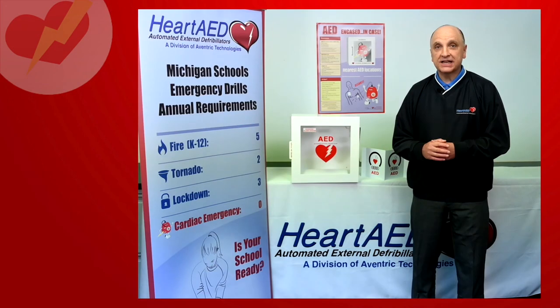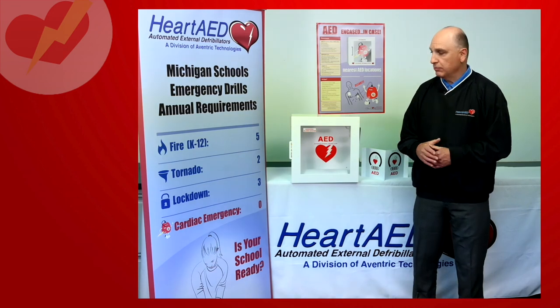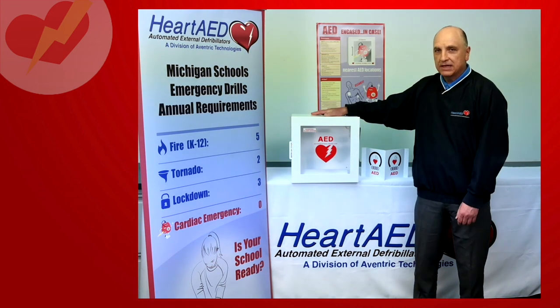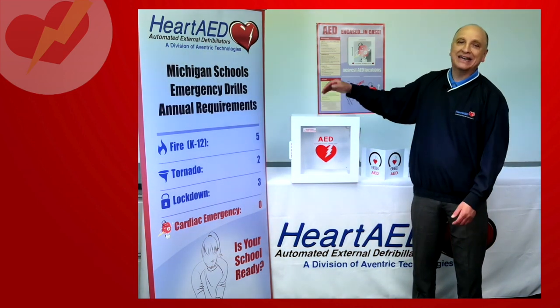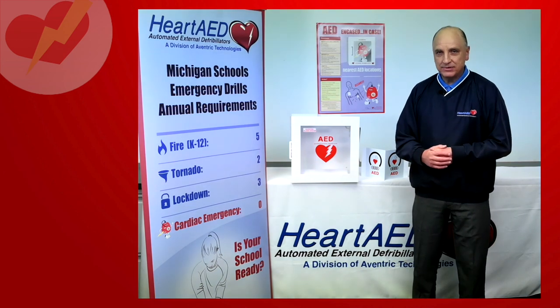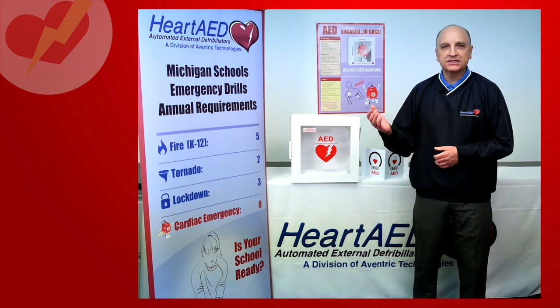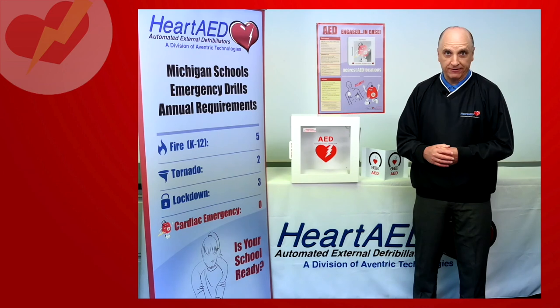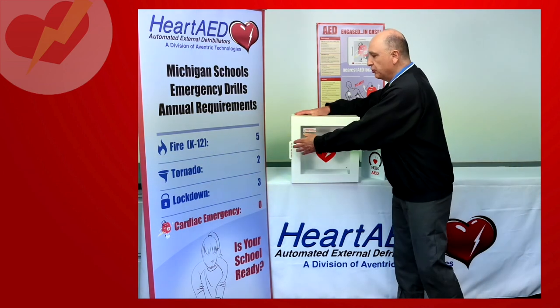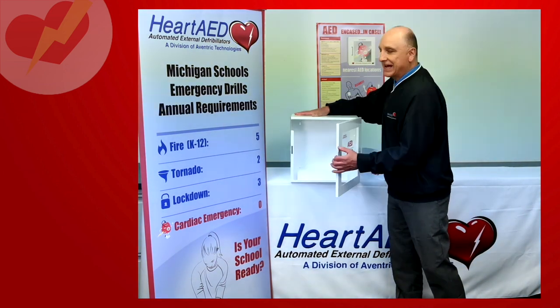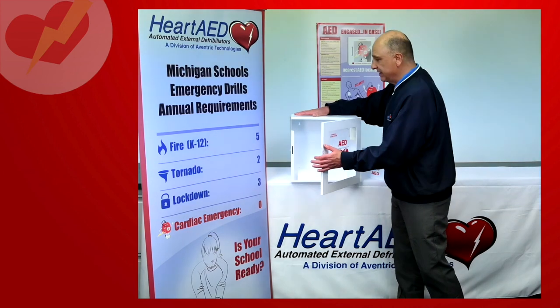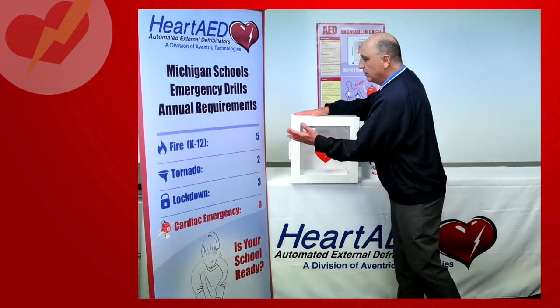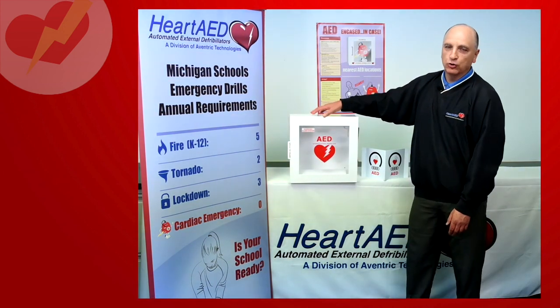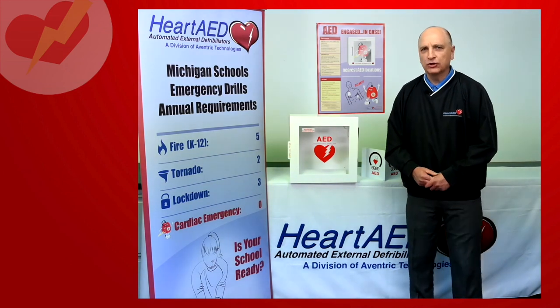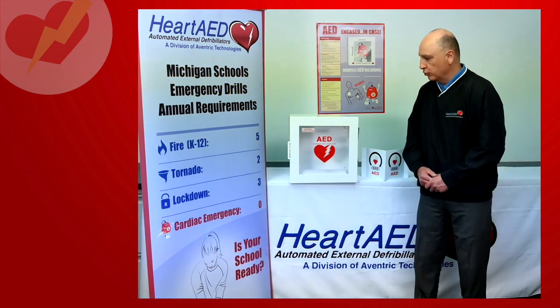A couple last items as it relates to your automated defibrillator. They're mostly stored in a wall cabinet. AED wall cabinets do not have locks on them. You may see keyholes, but that's basically to turn an alarm on and off. Most AEDs, when you open the door, an alarm will sound, just letting you know that somebody has accessed it. When you close it, more often than not, they go off. Some may not, but more often they go off with the closing of the door.